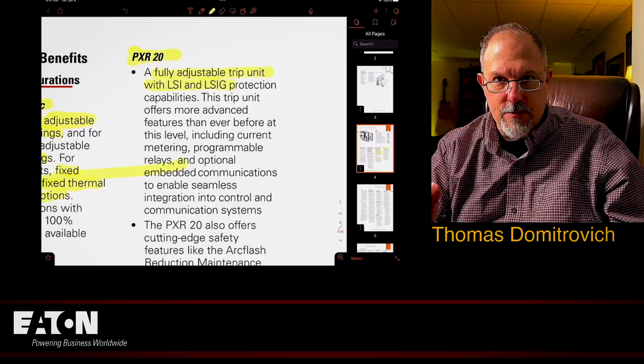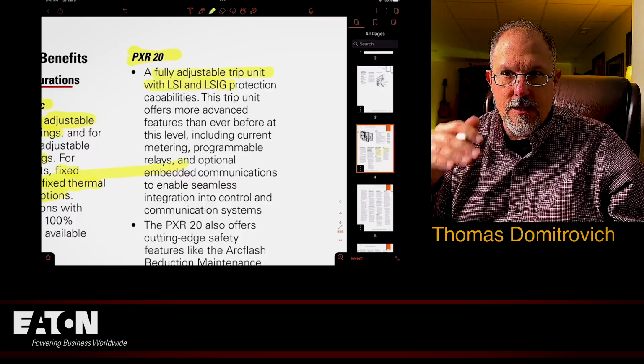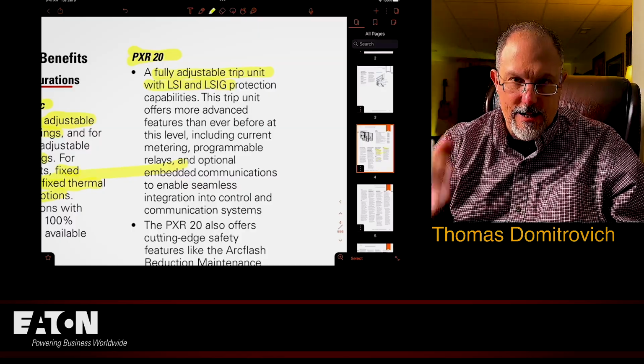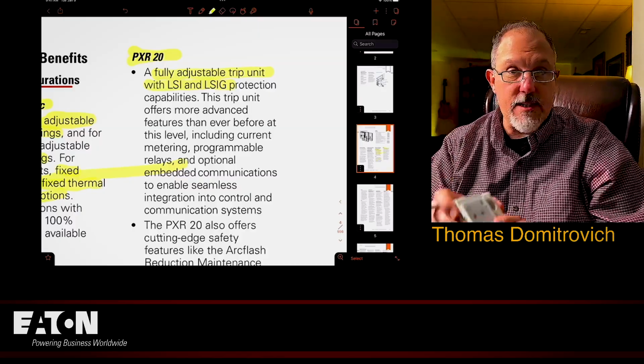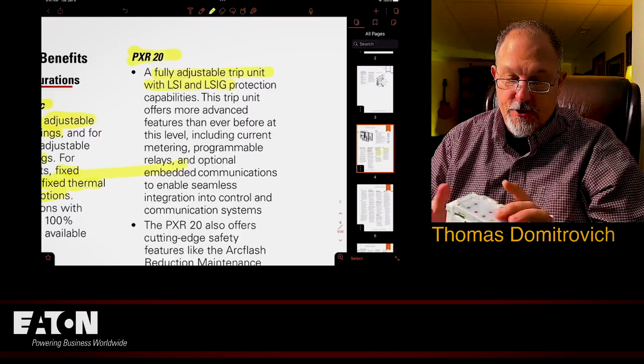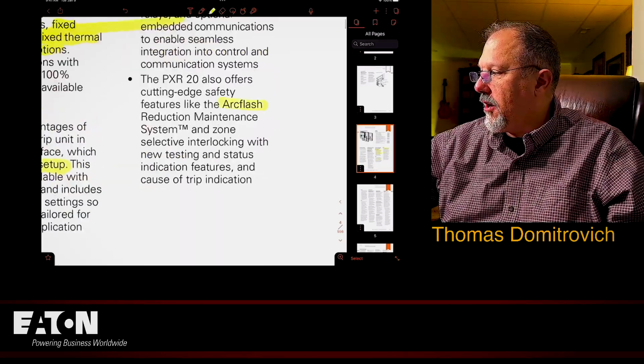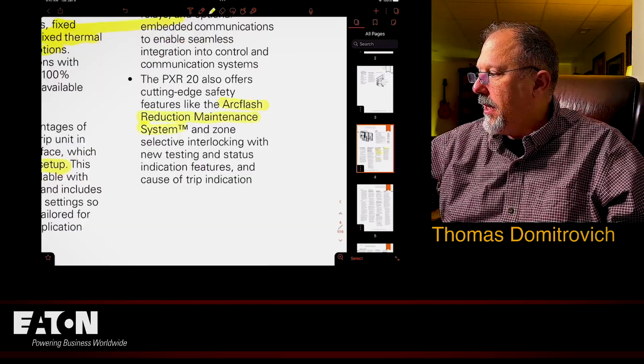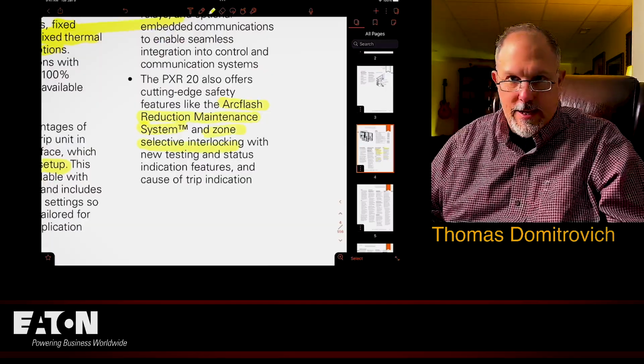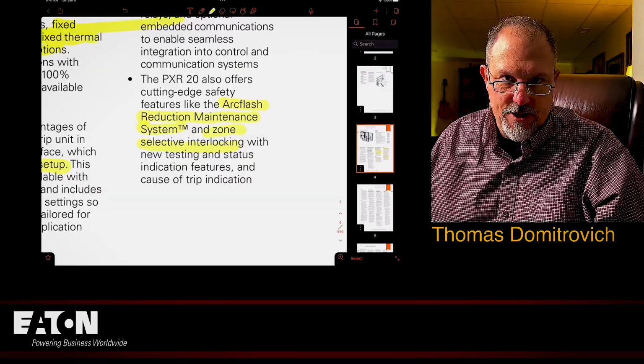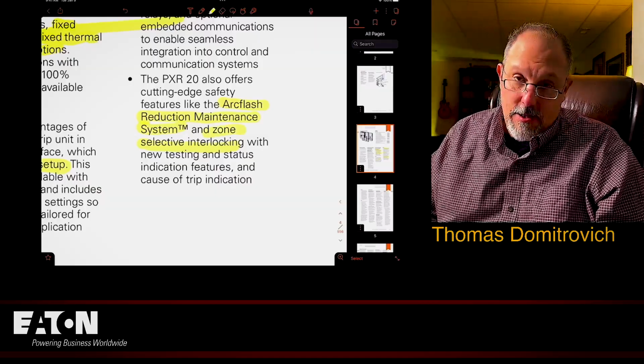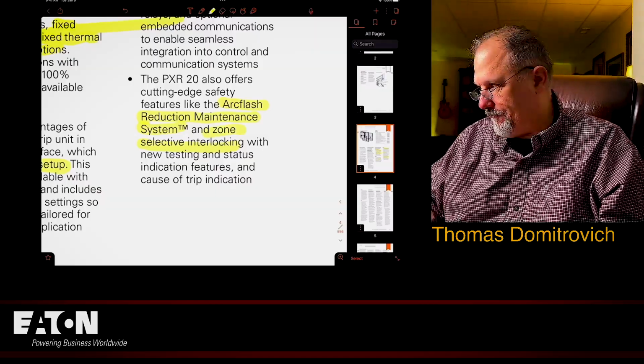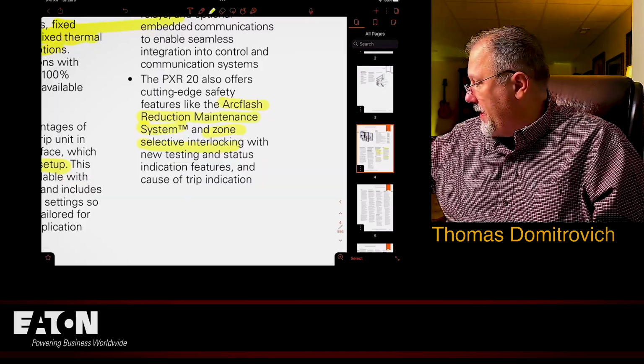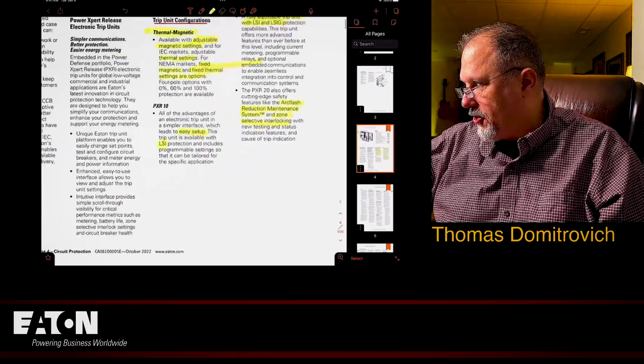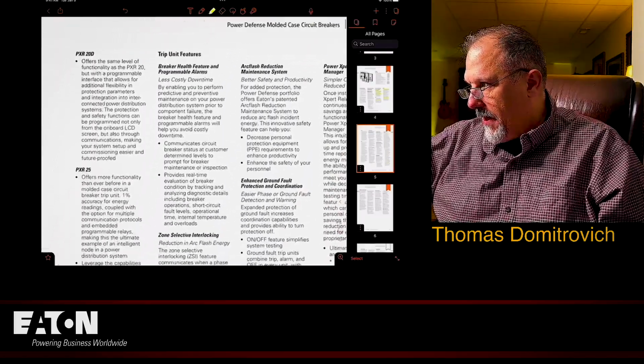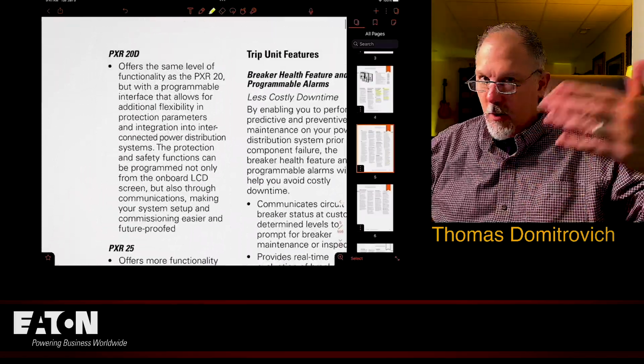A is for arc flash reduction. L is for long time. S is for short time. I is for instantaneous, and G is for ground fault. So this is packed with features. PXR20, again, there's your arc flash reduction maintenance system and zone selective interlocking. I keep calling it an arc flash reduction maintenance switch, but actually we call it an arc flash reduction maintenance system. All right, so there's your PXR20. And then obviously you can keep going up in functionality.